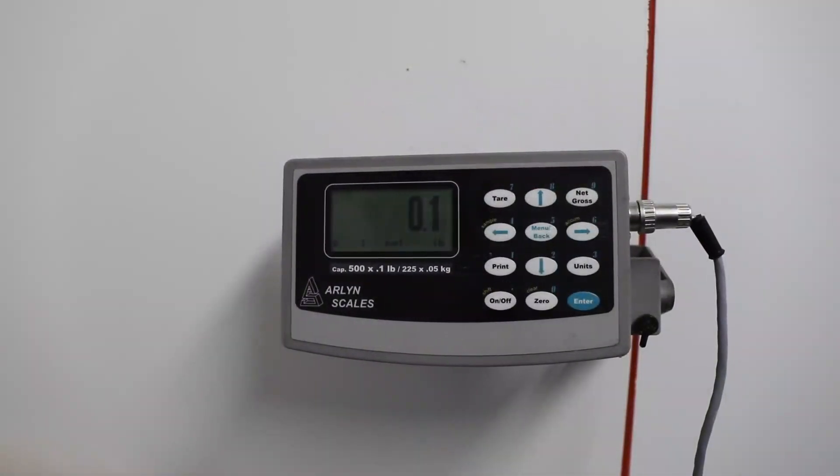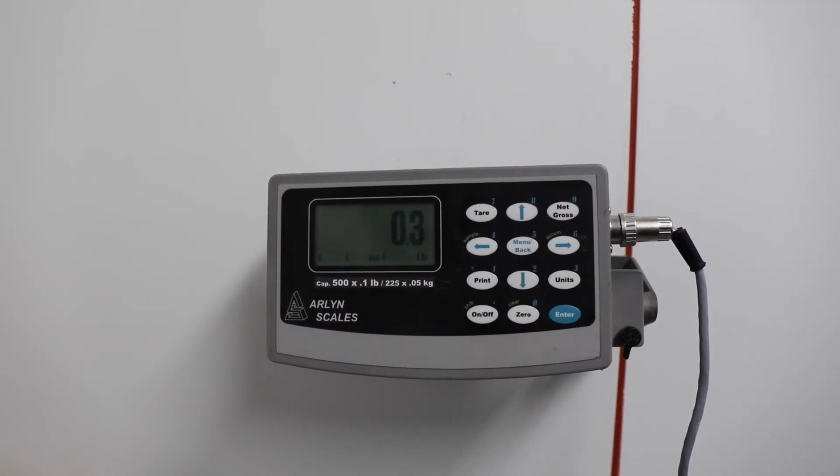On the faster side we get one pound recovered in about 34 seconds. An average over this whole test I got about 51 seconds per pound. Here's a real-time view of our scale as the liquid pours into the LP tank.